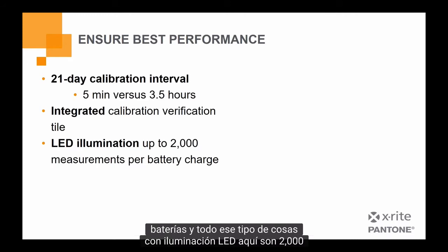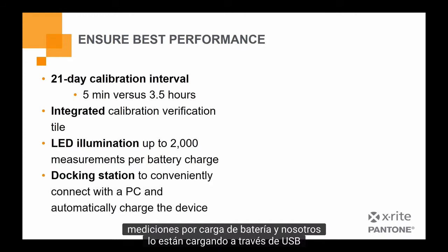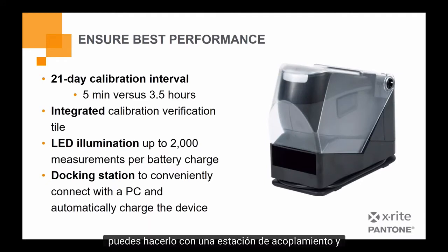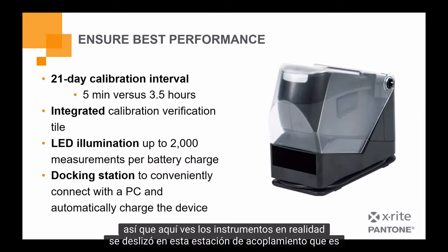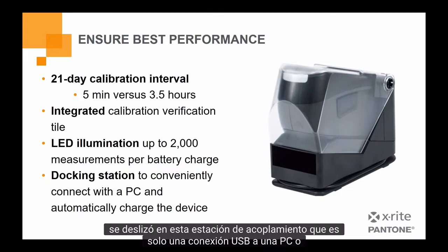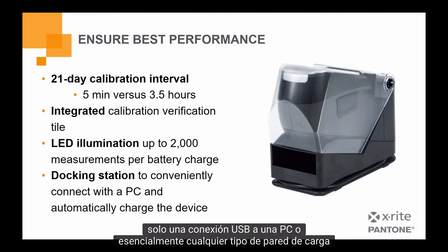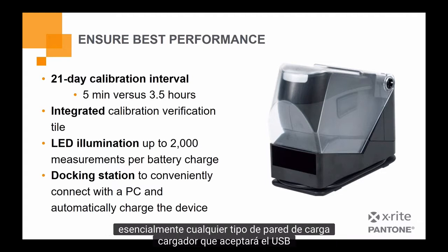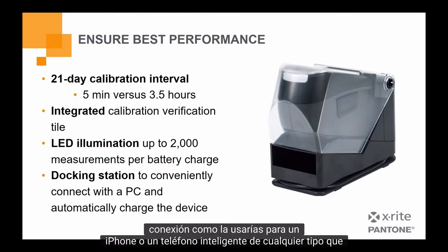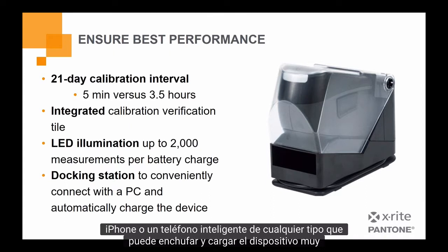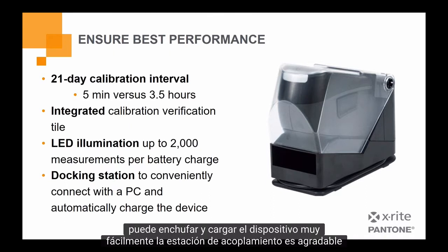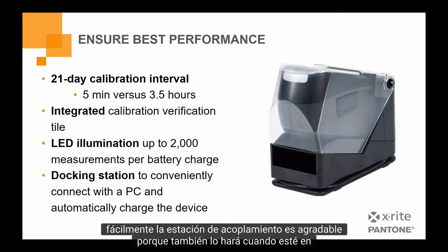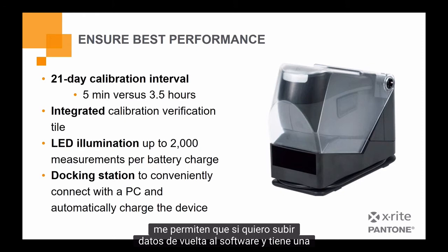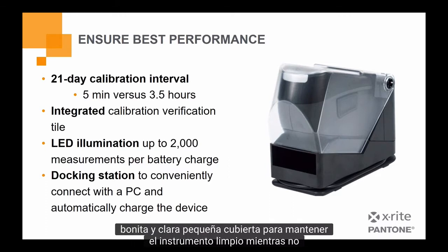With LED illumination here, it's 2,000 measurements per battery charge, and we are charging it via USB. You can do it with a docking station, and so here you see the instrument's actually slid into this docking station, which is just a USB connection to a PC, or essentially any kind of wall charger that will accept the USB connection, like you would use for an iPhone or a smartphone of any kind. You can plug in and charge the device very easily. The docking station's nice because it will also, when it's in there, allow me, if I want to, to upload data back to the software. And it's got a nice clear little cover on it to keep the instrument clean while it's not being used.